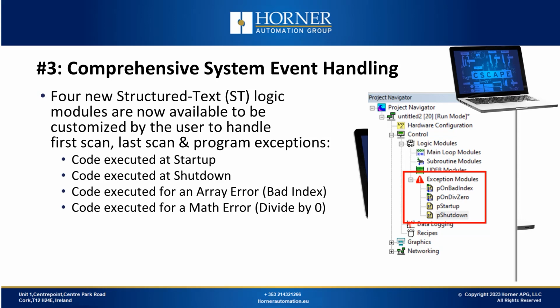Now we'll discuss enhancement number 3, comprehensive system event handling. In an enhanced IEC project navigator, you'll find the standard logic modules for your main loop and subroutines, but there are 4 additional modules at the bottom dedicated to exceptions. These structured text-based modules serve specific purposes. Firstly, there's one for handling startup events, allowing you to execute code whenever the controller starts up. Secondly, there's a dedicated module for shutdown events, enabling code execution during controller shutdowns.